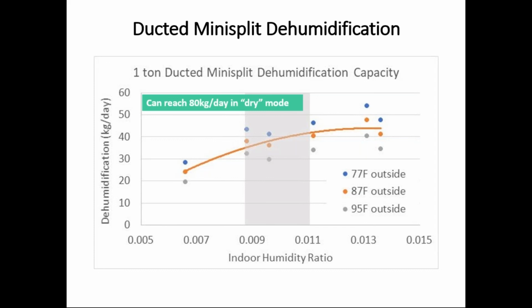The more humid it is inside, so this gray area is roughly where most people feel comfortable, say 50 to 60% relative humidity with about, say, 70, 72, 74 degrees inside. And then an outside temperature that the heat pump's working with, ranging from about the 70s up to the 90s. And so some impact on how hard the unit has to work. So as it gets hotter outside, a little less moisture capacity, but pretty significant moisture capacity on a per ton basis. Now, these units also typically have a dry mode or a dehum mode. And from the units that we've collected data from, we've seen where these might reach a moisture handling capacity of up to about 80 liters per day.